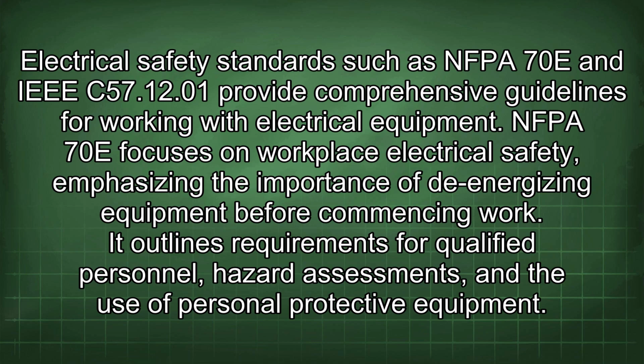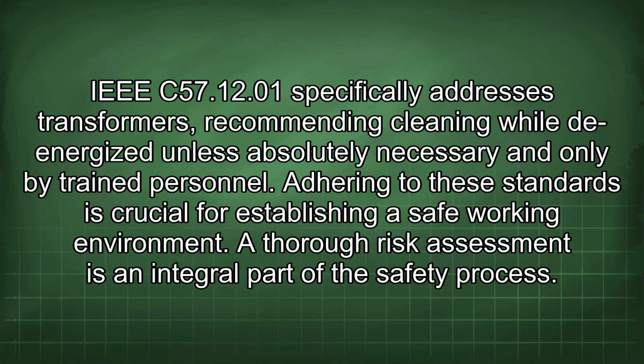Electrical safety standards such as NFPA 70E and IEEE C57.12.01 provide comprehensive guidelines for working with electrical equipment. NFPA 70E focuses on workplace electrical safety, emphasizing the importance of de-energizing equipment before commencing work. It outlines requirements for qualified personnel, hazard assessments, and the use of personal protective equipment. IEEE C57.12.01 specifically addresses transformers, recommending cleaning while de-energized unless absolutely necessary and only by trained personnel. Adhering to these standards is crucial for establishing a safe working environment.